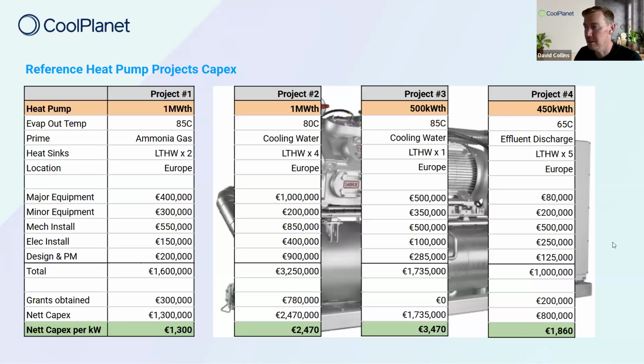And then this other final unit here on the slide is again about 0.5 megawatt, producing at a lower temperature, but it's for a space heating application in a pharmaceutical site. It had 5 heat sinks associated with it. And I suppose the interesting one about this is it was recovering heat at a lower temperature, but it was actually recovering from waste effluent that was being discharged to drain or to a treatment system. So again, the heat that was being recovered from there was being boosted through a heat pump and sent around via a new LTHW hot water network around the site. And it averaged just under 1,900 euros per kilowatt installed.